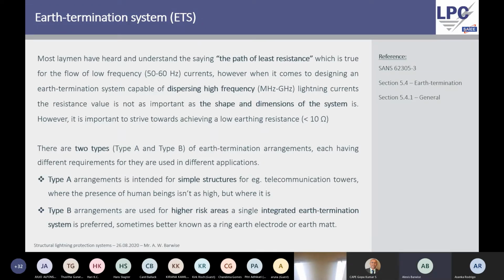Most laymen have heard the term, the path of least resistance. And I obviously conduct a lot of seminars, and I've heard quite interesting definitions or understandings of this word. But in essence, the concept was derived from how we all learned of electricity. And we learned of electricity really in a low frequency 50, 60 hertz type of domain, and there the concept is quite well understood. However, when we're dealing with lightning currents, which is a mega giga type hertz, it's a very high frequency current, the path of least resistance becomes almost the second or the third item.